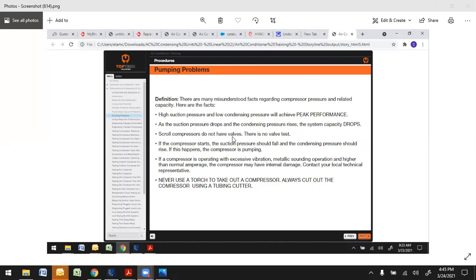Scroll compressors do not have valves, so therefore there is no valve test like with the older reciprocating compressors. If the compressor starts, the suction pressure should fall and the condensing pressure should rise. If this happens, your compressor is pumping.